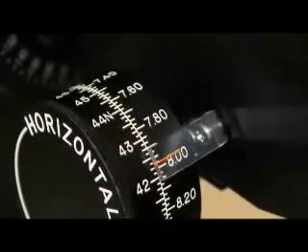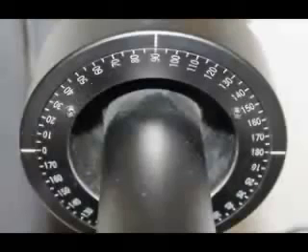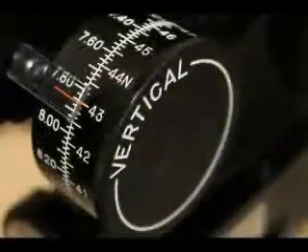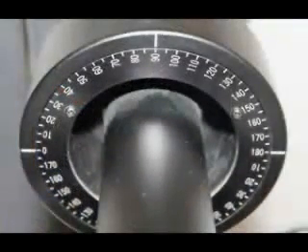Now follow these same exact steps for the left eye. The scale of the horizontal measuring drum indicates the dioptric power of the cornea along the horizontal meridian. Horizontal axes fall plus or minus 20 degrees around 180. The scale of the vertical measuring drum indicates the dioptric power of the cornea along the vertical meridian. The meridian indicators on the axis scale are white lines, and vertical axes fall plus or minus 20 degrees around 90.